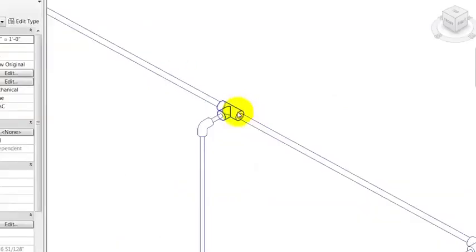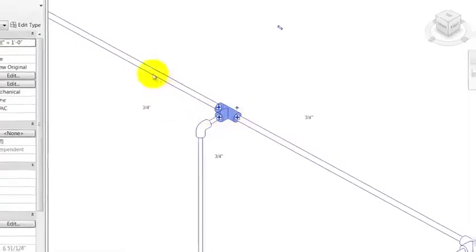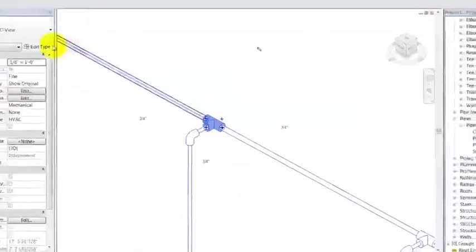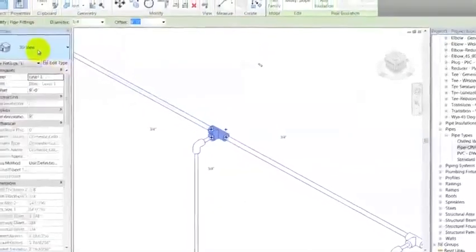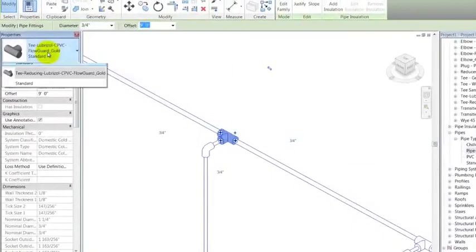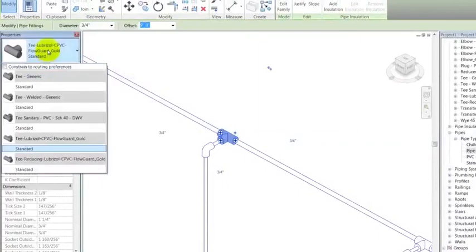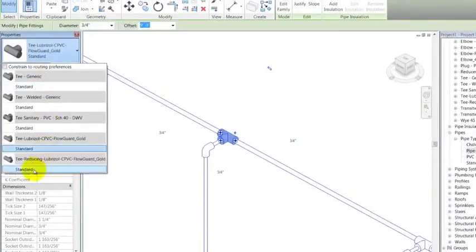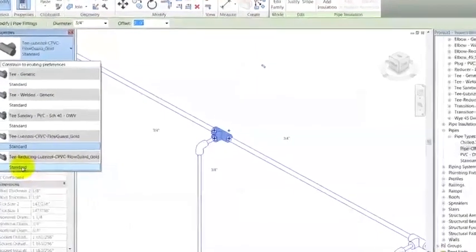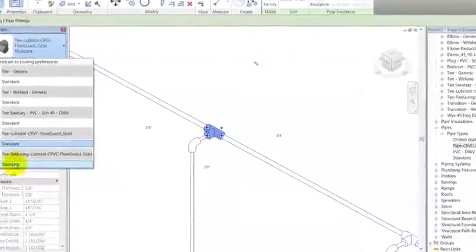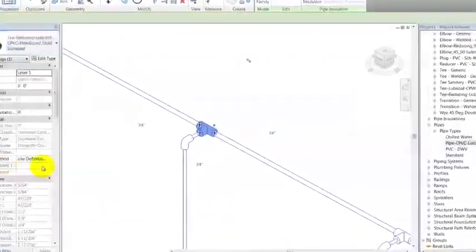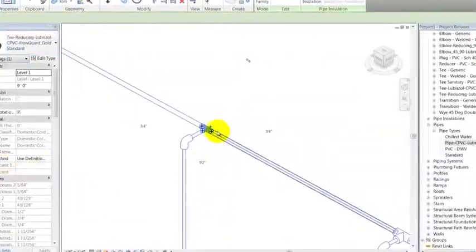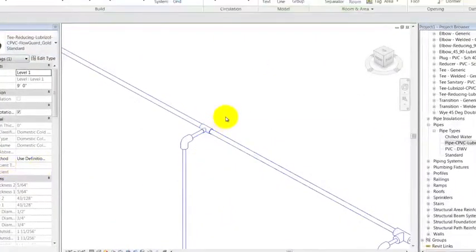After the 3D piping generates, let's zoom in to see the pipe sizes and fittings used. Notice the layout is not using reducing tees. Here is where they are changed manually. Select the desired tee and swap it for the reducing tee available in the Type Selector drop-down. Notice how it automatically changes in size.